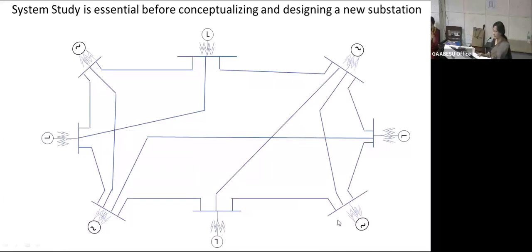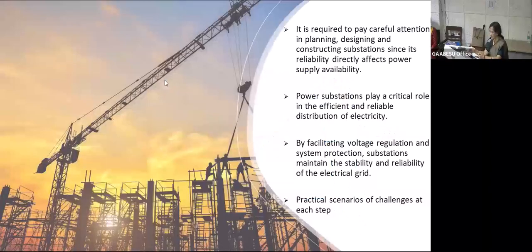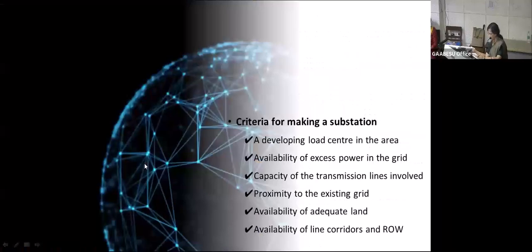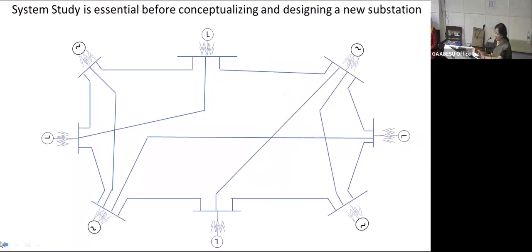Before coming to the concept of making a new substation, we have to study the system, look at the generation and load characteristics, and know how much the fault MVA is. We must know whether we have surplus generation to supply to the new consumers, and whether the transmission line has the capacity to carry the additional power. Successful operation of the entire power system depends to a considerable extent on the efficient and satisfactory performance of substations. It comprises power transformers, switchgear, control, protection, monitoring, and automation equipment. So it is required to pay careful attention in planning, designing, and constructing substations, since their reliability directly affects power supply availability.